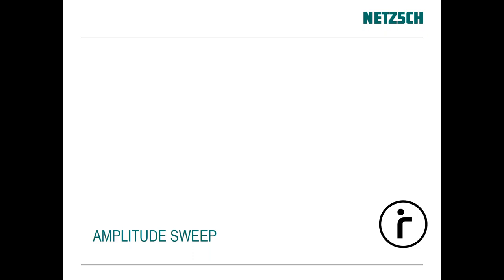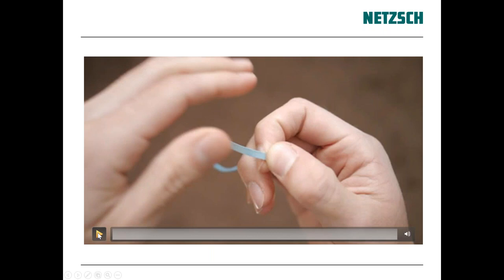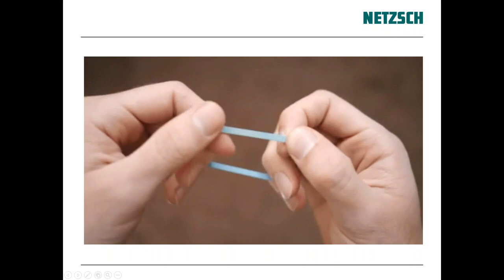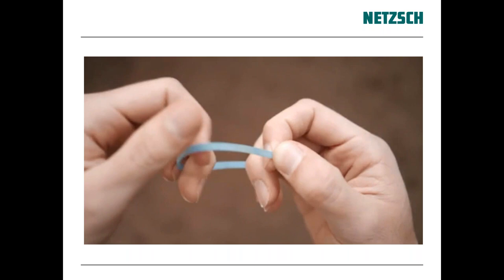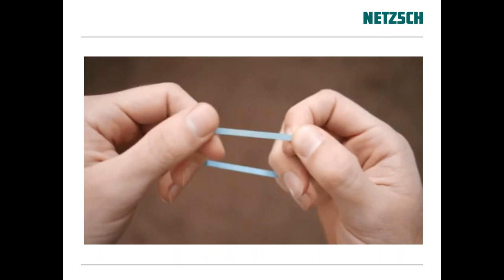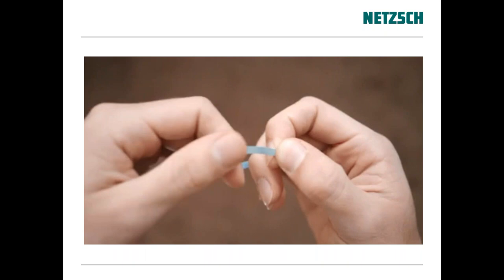We want to perform frequency response tests operating within the linear viscoelastic region. The LVR is similar to pulling a rubber band or putting weights on a spring — we're looking at how it stretches as a function of force. When we start deviating from linear behavior we've gone non-linear, and non-linear is where we reach the breaking point in the material.